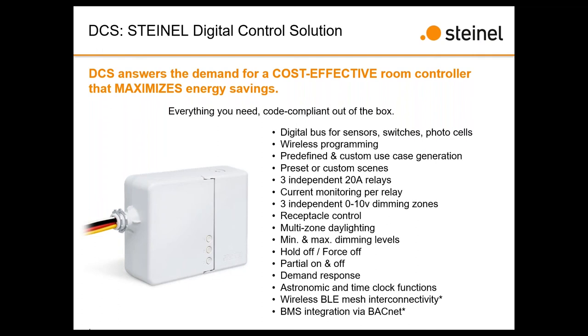What if I would like to take a large installation that has multiple different DCS devices? I can put a master on-off switch for the entire location that goes across the DCSs, but I can program a single button that will allow me to turn off all the lights in, say, a restaurant, like a fast food restaurant. If I wanted to turn off the dining room, the kitchen, the bathrooms, the manager's offices, the coolers, all at once, the outside site lighting, whatever I wanted to do, I could program a single button on there that is the master backdoor switch.